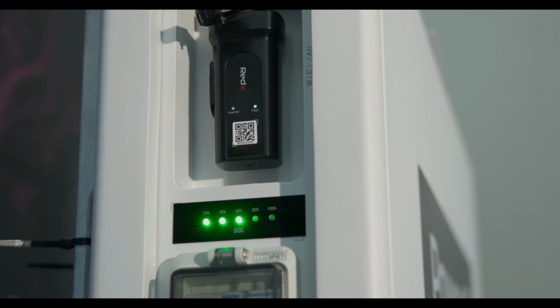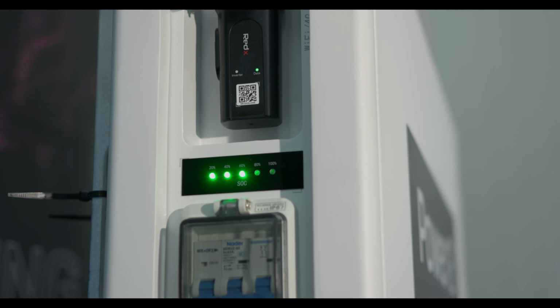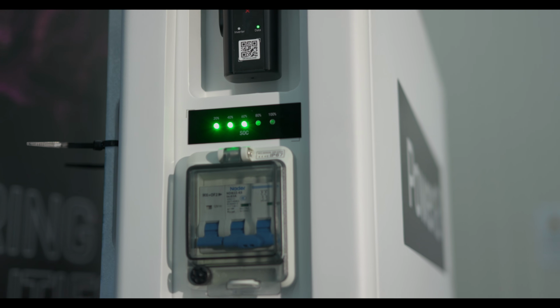well, this is the other business side of the inverter. This is the battery isolator. So switching this breaker here turns off both the BMS and the battery positive and negative connectors. Now, why does it turn the BMS off as well? Well, there's a BMS in every battery module, and you don't want it wasting power running when you actually turn the batteries off. So that's a clever idea.